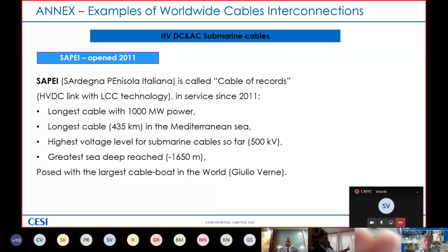Let's start with one of the old, not the oldest, but one of the old: Sardinia to the Italian peninsula, that at the time, in 2011, was named the cable of records because it was the longest cable with 1,000 megawatt power, the longest cable, 435 kilometers, in the Mediterranean Sea. The highest voltage level for a submarine cable so far, 500 kV, and this is a critical issue. The greatest sea depth reached is minus 1,650 meters. And this was laid by the Giulio Verne, the first on the left, from Prysmian. And we will come back to the depth of the sea, because this is a critical issue we will discuss later on.